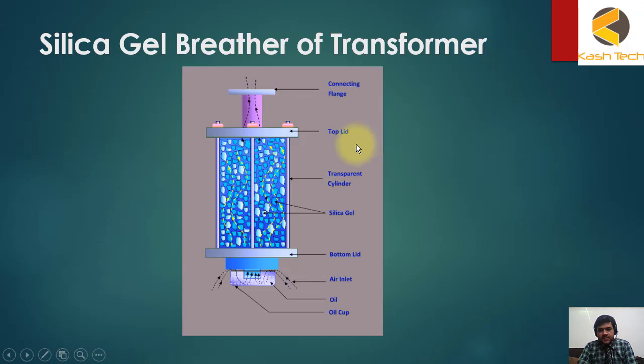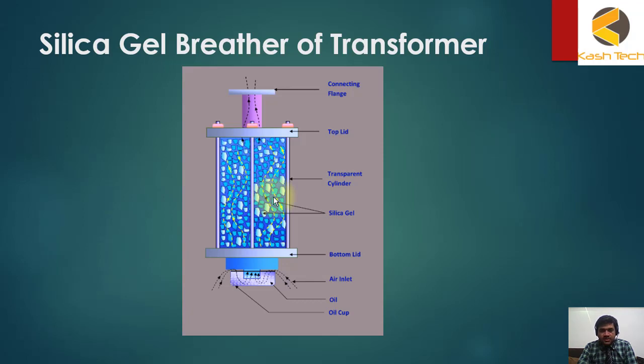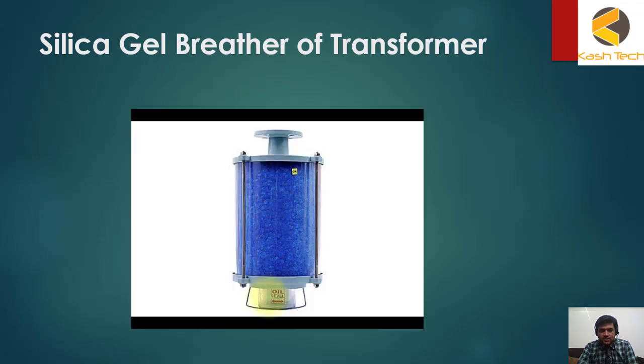This example shows the connecting flange, top lid, transparent cylinder, and silica gel which is in blue color, followed by the bottom lid, air inlet, oil, and oil cup. When the silica gel absorbs moisture, its color changes from blue to pink. When you observe that color change, you have to replace or reactivate the silica gel.